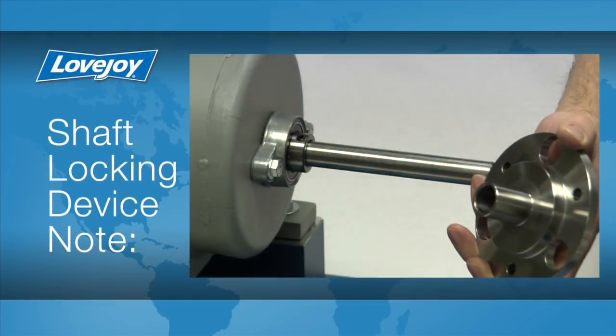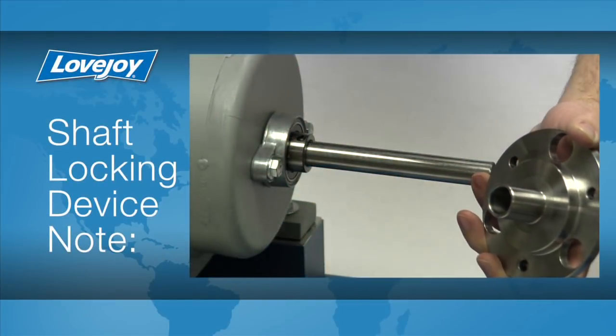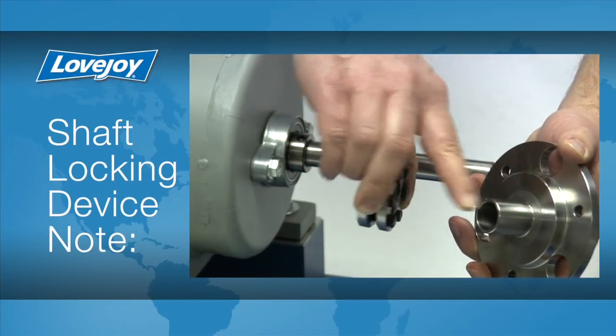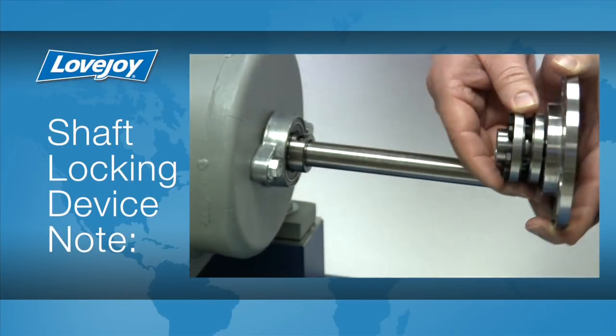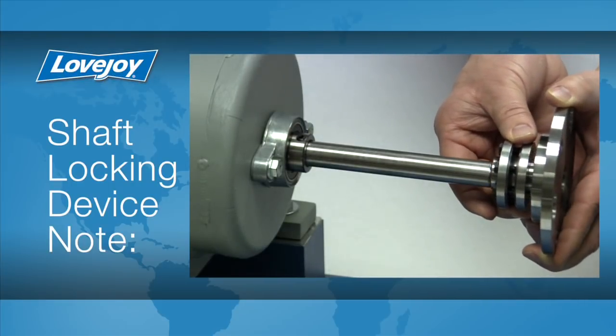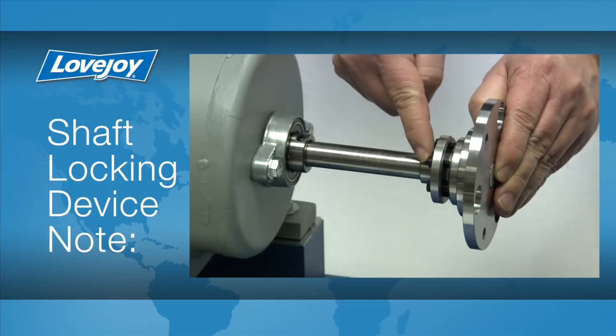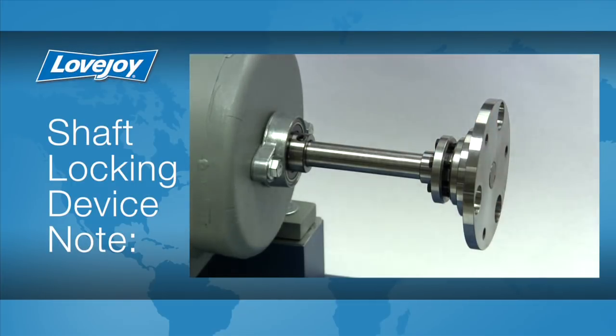When installing a disc coupling where one or both hubs are to be secured on the shaft using an SLD, or shaft locking device, locate the SLD on the recess machined into the exterior surface of the hub. Then slide the hub on the shaft to the desired location and tighten the SLD bolts using the procedures and tightening torque specified in the SLD installation guide. The SLD is a keyless alternative to a clamping style hub and allows for axial and rotational adjustments to be made after the coupling has been installed.